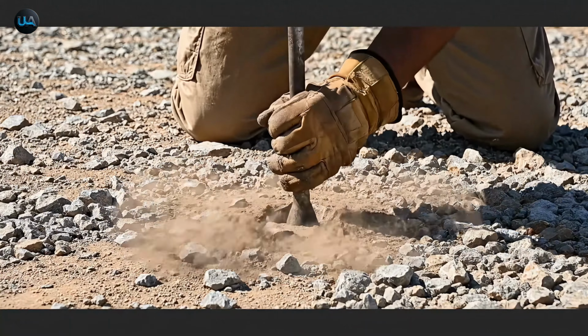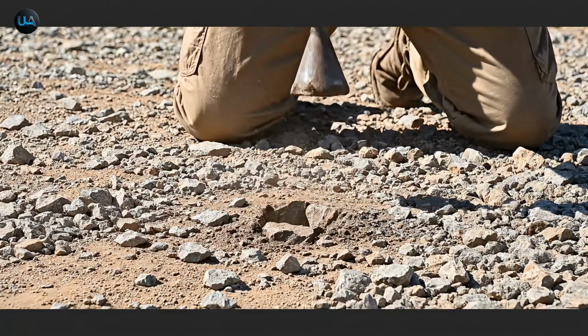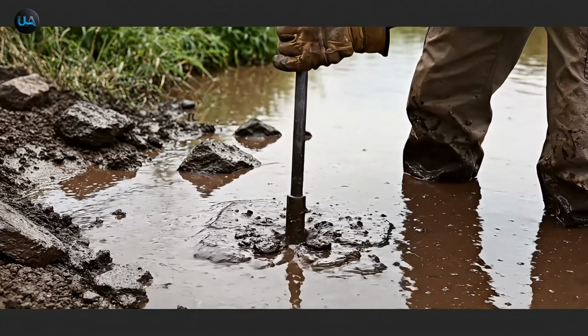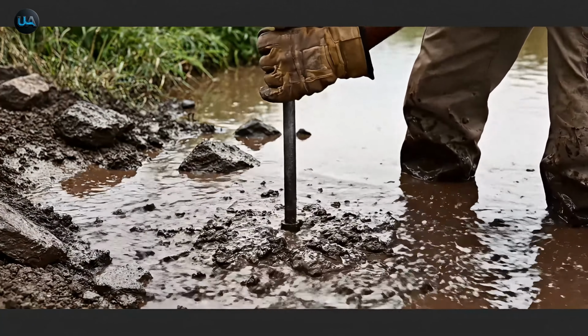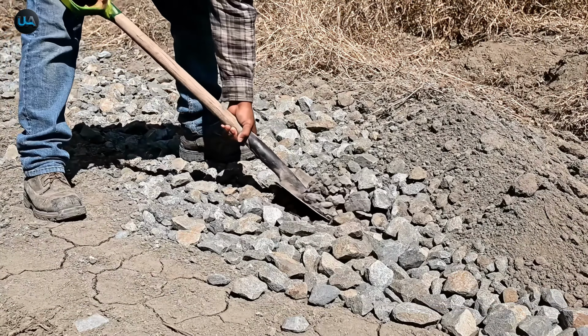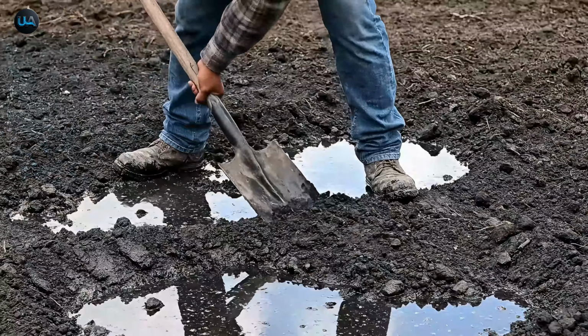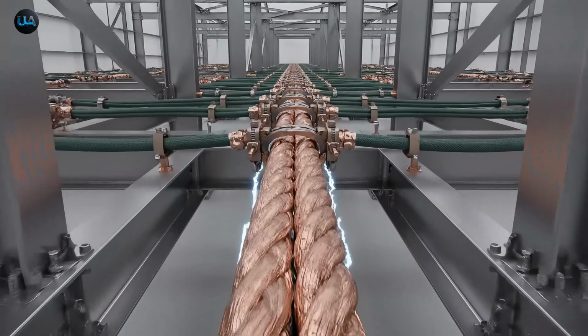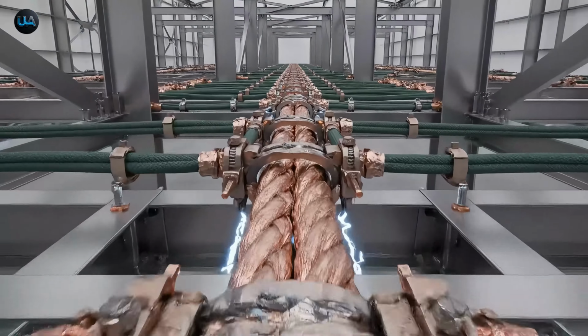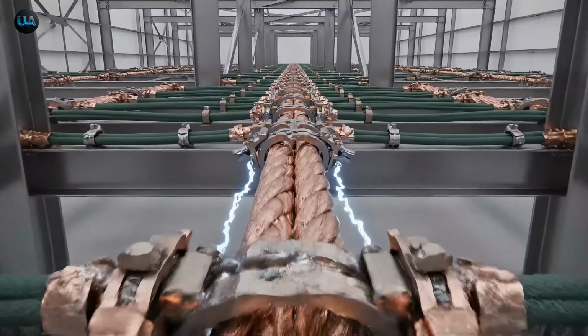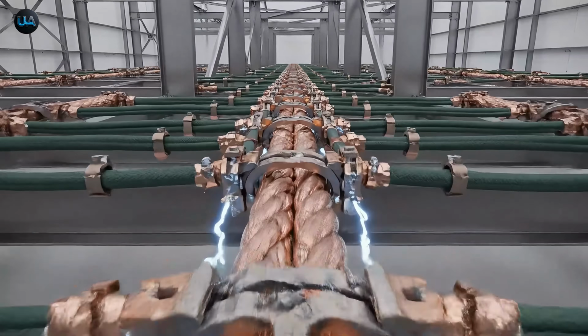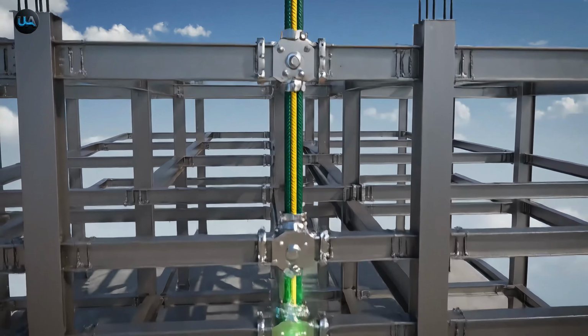The effectiveness of the system depends entirely on the Earth's resistance. Dry, rocky soil has poor conductivity, requiring multiple rods or chemical enhancements. To ensure proper bonding, all metal parts, pipes, conduit, and structural steel are connected to the grounding electrode system.